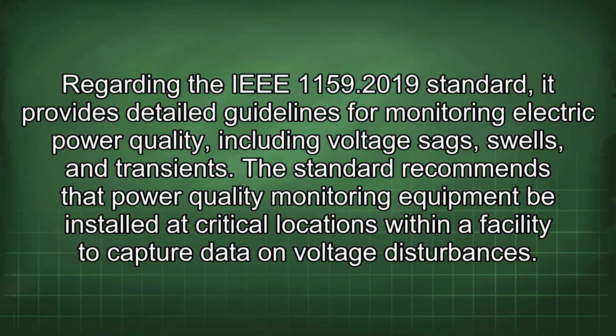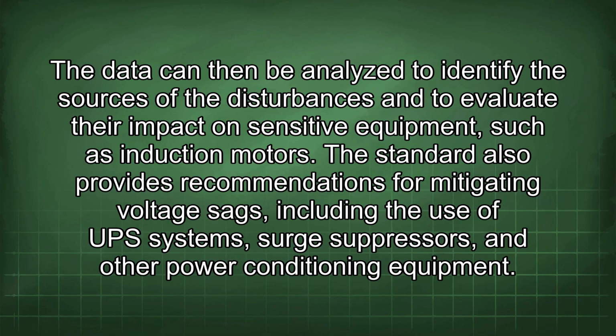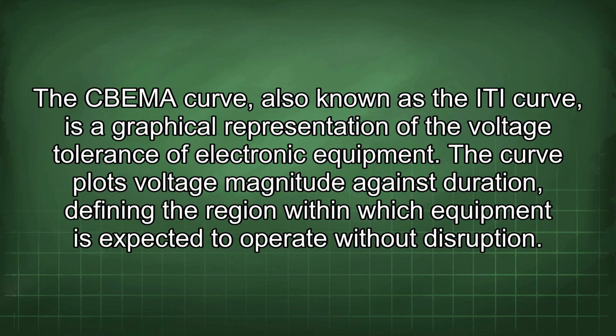The standard recommends that power quality monitoring equipment be installed at critical locations within a facility to capture data on voltage disturbances. The data can then be analyzed to identify the sources of the disturbances and to evaluate their impact on sensitive equipment, such as induction motors. The standard also provides recommendations for mitigating voltage sags, including the use of UPS systems, surge suppressors, and other power conditioning equipment.